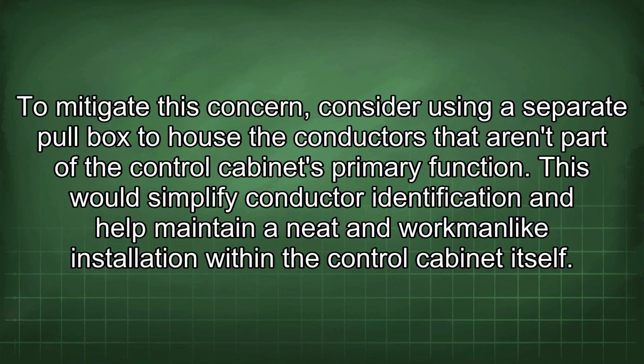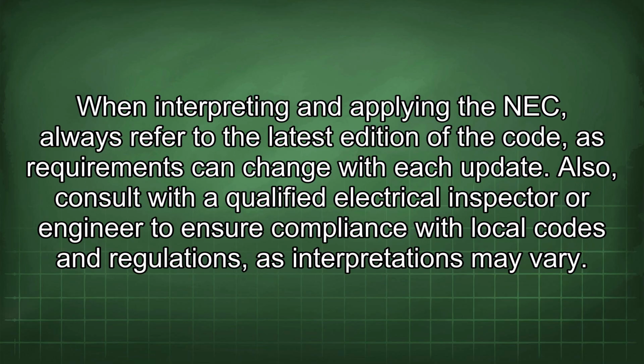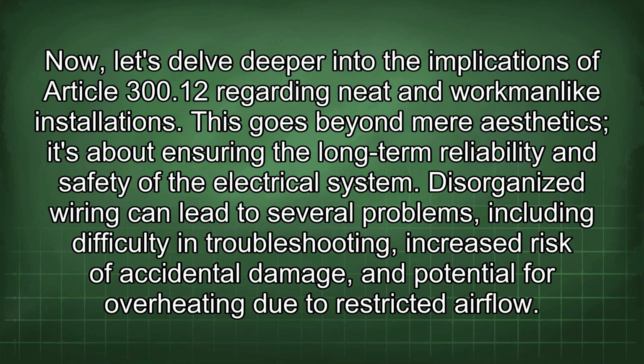To mitigate this concern, consider using a separate pull box to house the conductors that aren't part of the control cabinet's primary function. This would simplify conductor identification and help maintain a neat and workmanlike installation within the control cabinet itself. When interpreting and applying the NEC, always refer to the latest edition of the code, as requirements can change with each update. Also, consult with a qualified electrical inspector or engineer to ensure compliance with local codes and regulations, as interpretations may vary. Now, let's delve deeper into the implications of Article 300.12 regarding neat and workmanlike installations.